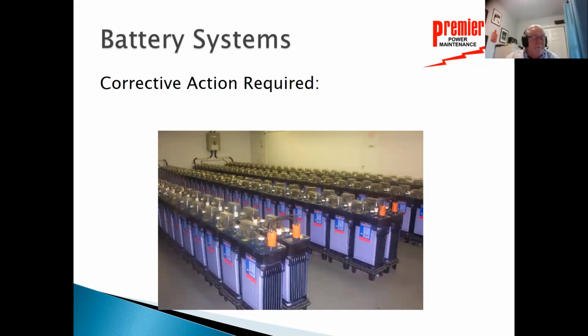Individual cell readings, and people just truly don't understand this sometimes. If you look at the overall string voltage and divide that by the number of cells, you will get a voltage for the cells. Say, for instance, each cell is about 2.24 volts per cell, and that's a typical float voltage for a lead acid battery. If the voltage of any one of these cells varies by more than 0.05 volts, and that's a pretty minute variance, if there's a variance of 0.05 of a volt on one of those cells from the string average, then that's reason to take corrective action.